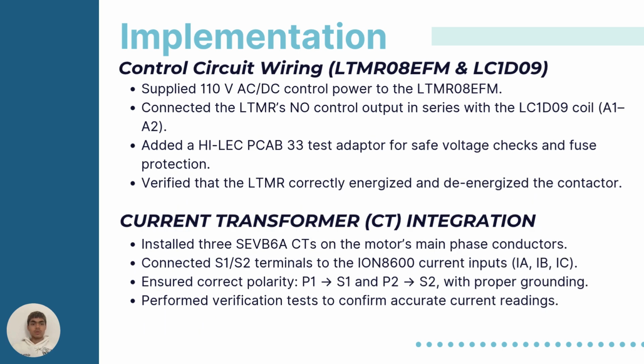Yep. So control circuit wiring. The control circuit refers to the relay and the contacts. So this prevents any faults into the motor and power analyzer. Current transformer integration, which steps down the current that is being fed into the power analyzer.